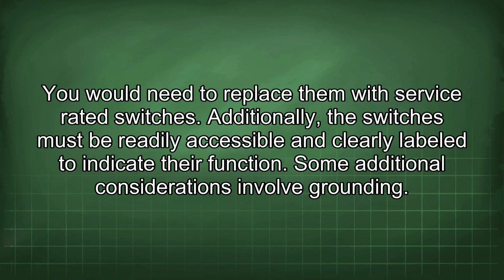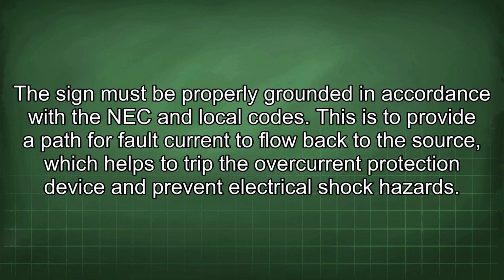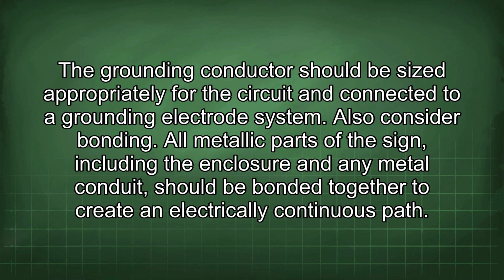Some additional considerations involve grounding. The sign must be properly grounded in accordance with the NEC and local codes. This is to provide a path for fault current to flow back to the source, which helps to trip the overcurrent protection device and prevent electrical shock hazards. The grounding conductor should be sized appropriately for the circuit and connected to a grounding electrode system.